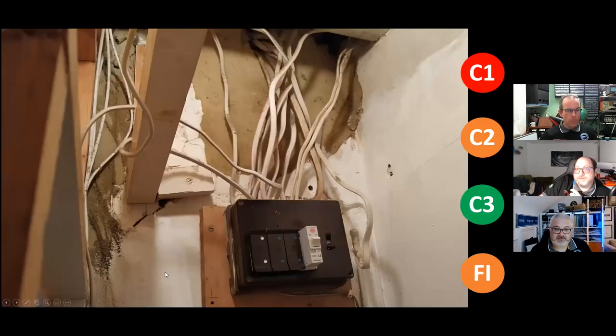Right, moving on. We're nearly there, by the way. Right, another Wylex consumer unit, fuse box, whatever. Someone's upgraded one of them, if you want to call it that, with that lovely 6-amp thing at the end. And then, of course, the main problem here is all of those cables spewing out the top. Was all this boxed in and the boxing's been taken away? No, that's actually how it was. It's in a cupboard. So you open the cupboard door, this is what you find. Well, at least you've got slack to remake the board off. Yeah. I mean, one of those cables isn't even in the board on the right-hand side there. It's just hanging down. I know you'd be looking at prescribed zones and stuff for cables coming down, but for me, that is desperate for some trunking.